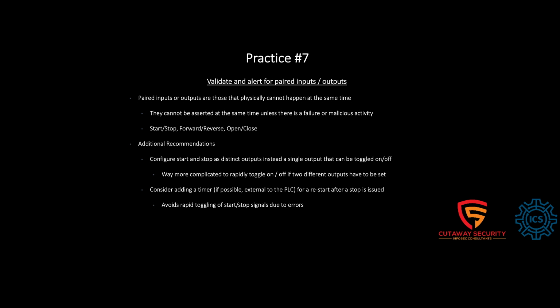You command the valve to go open, but the closed limit switch doesn't change while the open limit switch comes on, then you know for a fact that the closed limit switch is faulty. So historically, some were configured for that kind of benefit, but because we're now saying there is a security benefit to it, if you did not include that on all the process controls, you could probably add it. And this doesn't need any additional field hardware or IO. It's just taking advantage of what you already have and comparing them to say, I shouldn't get these two at the same time. I'm getting one, which is good. I'm getting the other, which is good, but I shouldn't get both at the same time. So this just needs one additional piece of logic that you can replicate across the board, without any additional hardware.